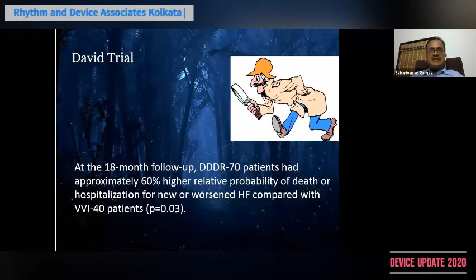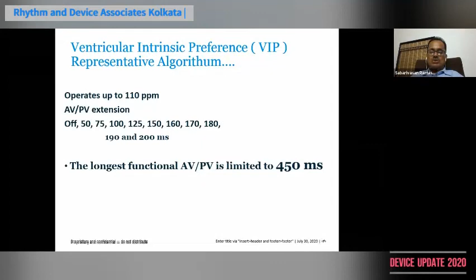How to pace? Only when needed. So there are a lot of algorithms coming into play which can help the physician achieve this objective. VIP is from Abbott, MVP from Medtronic, VP suppression from Biotronik, AV search hysteresis from Boston Scientific. So every company has an algorithm with the objective of reducing unnecessary pacing in the ventricle. I will take one representative algorithm, ventricular intrinsic preference, or VIP, and this operates up to 110 beats per minute. Every algorithm has a range, and sometimes it doesn't go all the way to the maximum tracking rate. The idea is to extend the sensed AV delay or paced AV delay now and then, so that you will be able to get the intrinsic conduction through.